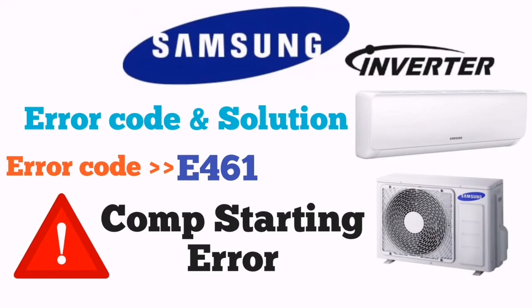When you see error E461, or your LED 2 is blinking, it means it's a compressor starting error. First of all, you have to check the connection of your UVW or running, start and common, whether the connection is good or not. If your connection is good, then there is another fault. Then you have to download the EEPROM data in your outdoor PCB. After downloading, if you start and it's showing the same error again, it means you have another problem.